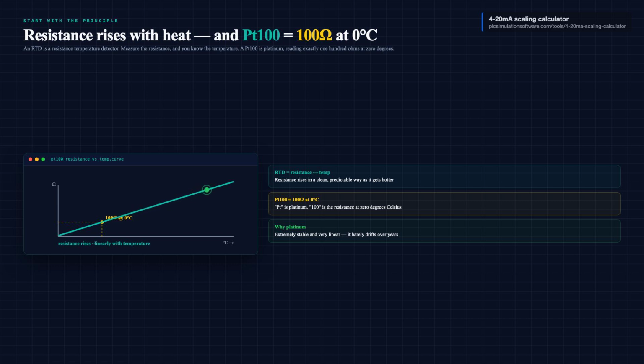The Pt100 is the most common type. The Pt is platinum, and the 100 is the key number. It reads exactly 100 ohms at 0 degrees Celsius. Why platinum? Because it is extremely stable and very linear. The resistance to temperature curve is almost a straight line, and it barely drifts over years of service. That is what makes a Pt100 accurate and repeatable, where a cheaper sensor would wander.